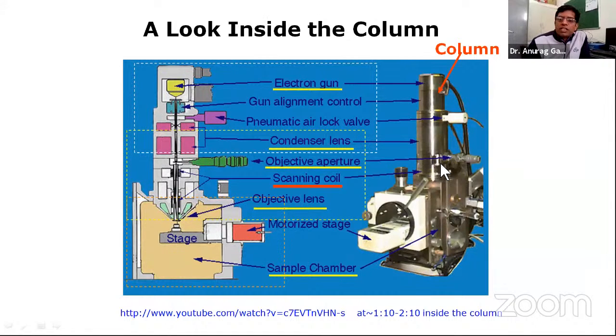Then the scanning coil basically controls the movement of your electron beam. And this is the motorized stage that comes out. If you want to change the sample, it will go inside the chamber and be aligned with the electron beam. This is the sample chamber. Within this whole chamber there will be a vacuum, so on the other side a vacuum system is attached, a molecular pump or turbomolecular pump. The vacuum order should be 10 to the power minus 10 torr. Then detectors are there, which will be used to get the image of the sample.